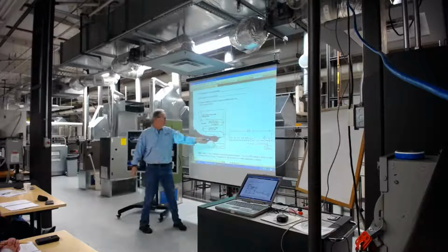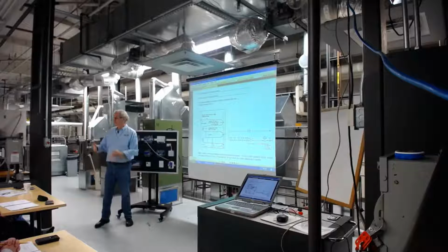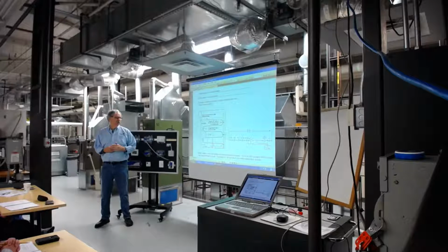The pressure switches, this is what I like: high static. High static cut out for heated air we're getting into. At that fan, you absolutely can run away. That duct was only rated for 3 inches, and this thing can deliver 6 inches. You're in serious trouble if you don't have a high static cut out. So all these safeties are very important.